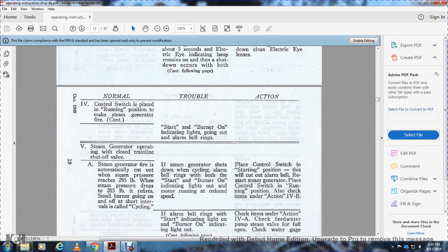All right, 5. Steam generator operating with the closed train line shut off valve. The steam generator fire is automatically cut off when the steam pressure reaches 295 pounds. When the steam pressure drops to 285, it refires. The small burner going on and off at intervals is called cycling.